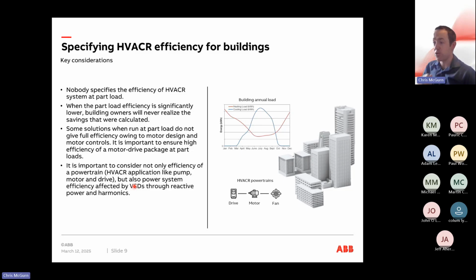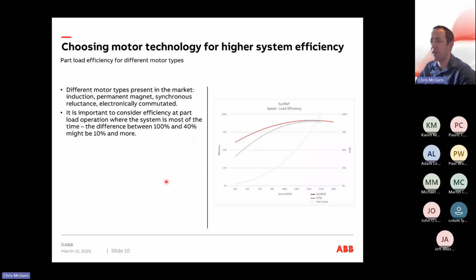And if they're not designed around an understanding of that part load, there can be a lot of losses within the efficiencies themselves. So it's important not only to consider the efficiency of a powertrain, but also the system efficiency of the VSDs through the power and the harmonics.